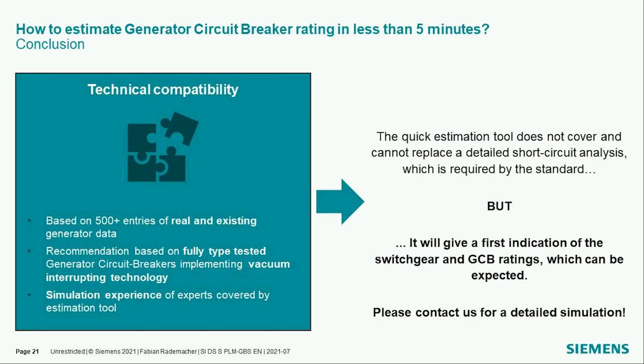The estimation tool has a technical compatibility with more than 500 entries of real and existing generator data, and it gets more every day. So the recommendation you get from this estimation tool is based on fully type-tested generator circuit breaker solutions and GBS solutions implementing vacuum interrupting technology. And it also covers the simulation experience we have gained over the last multiple years.